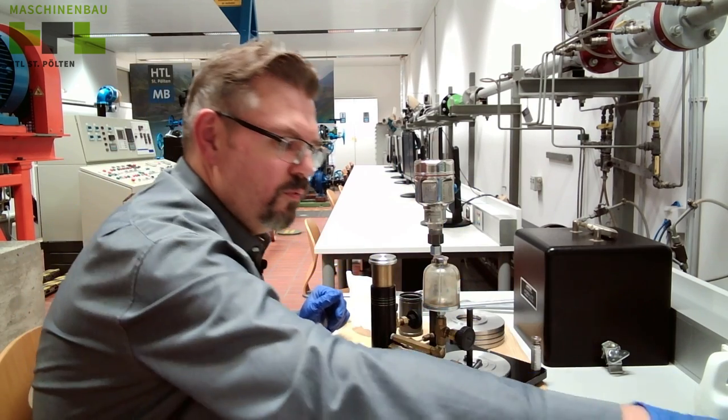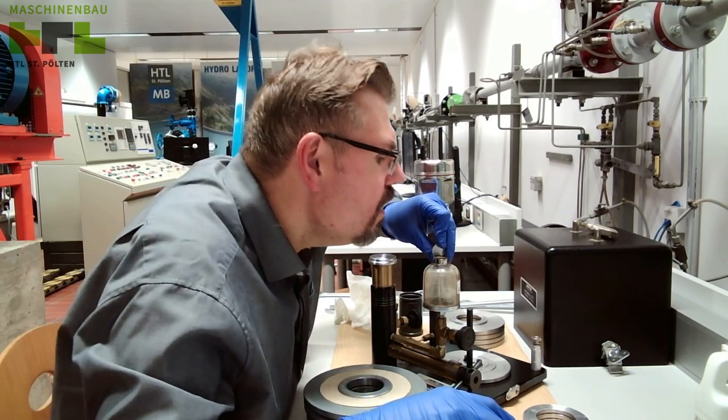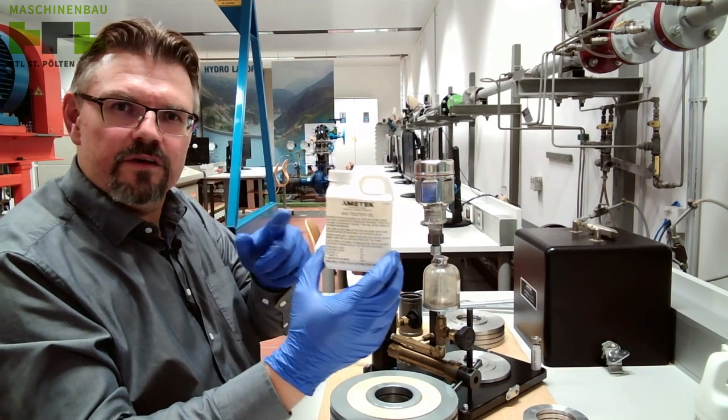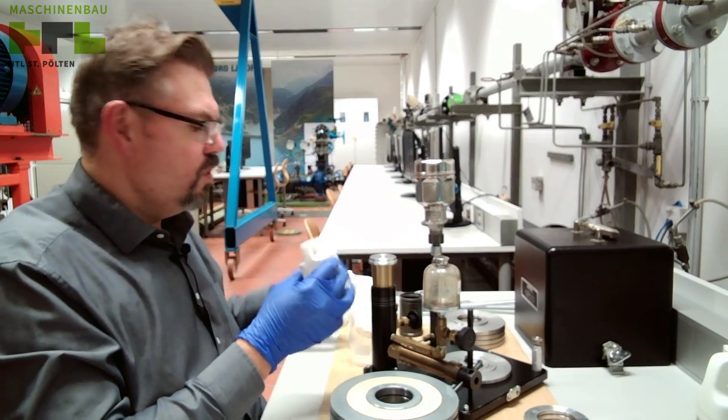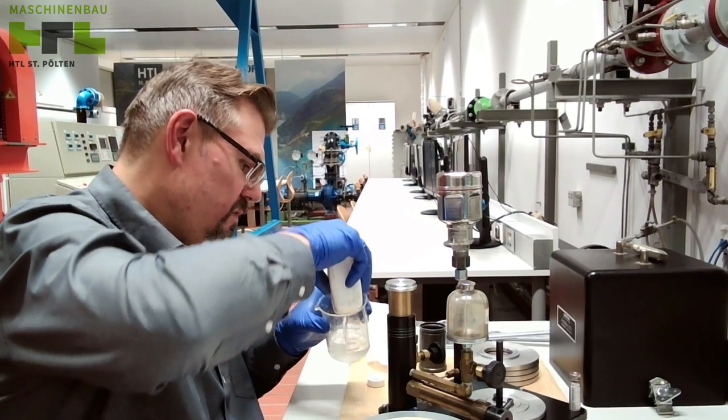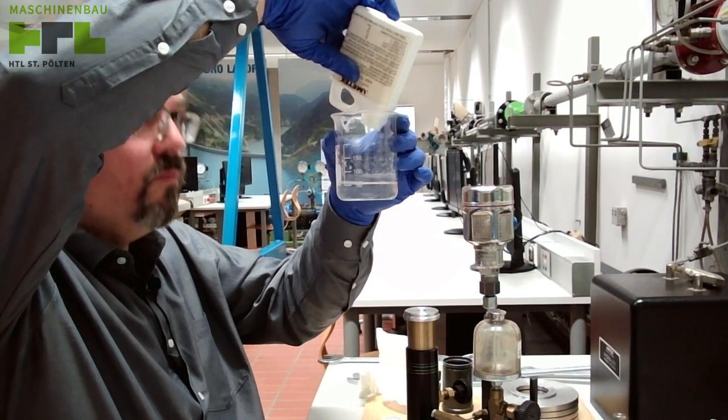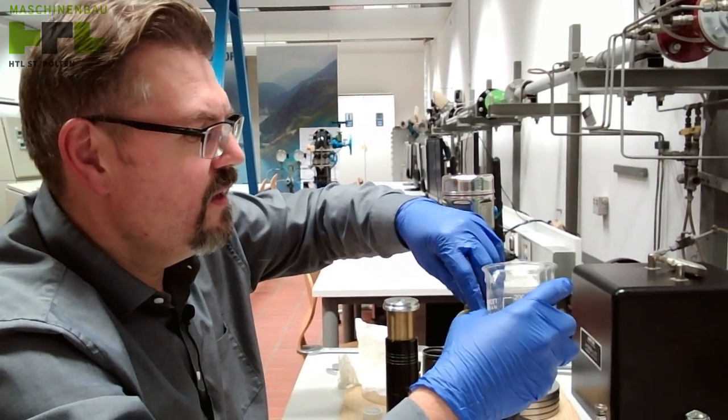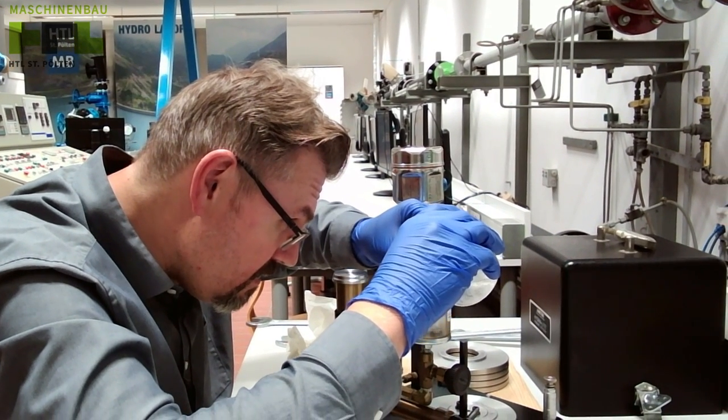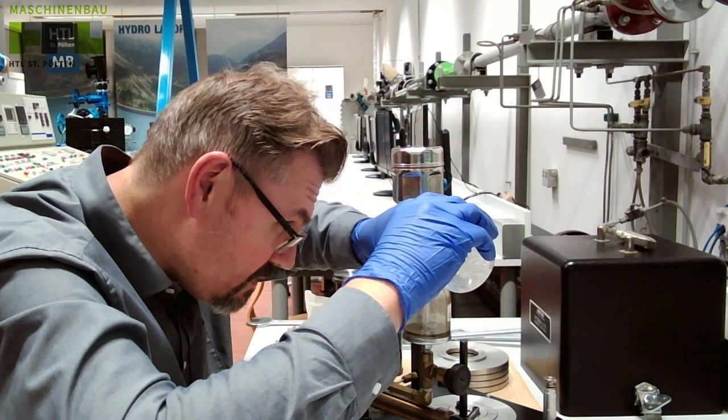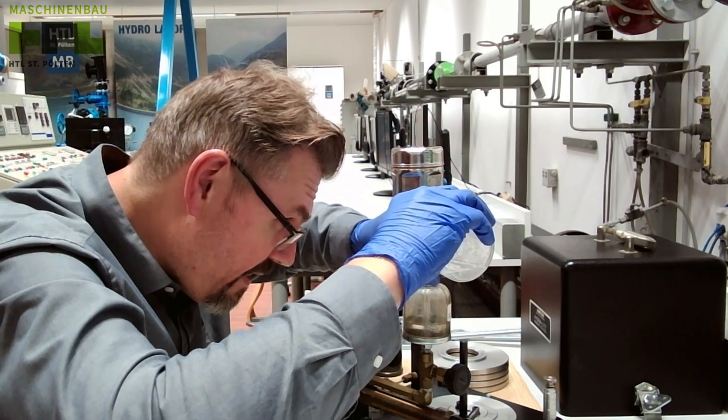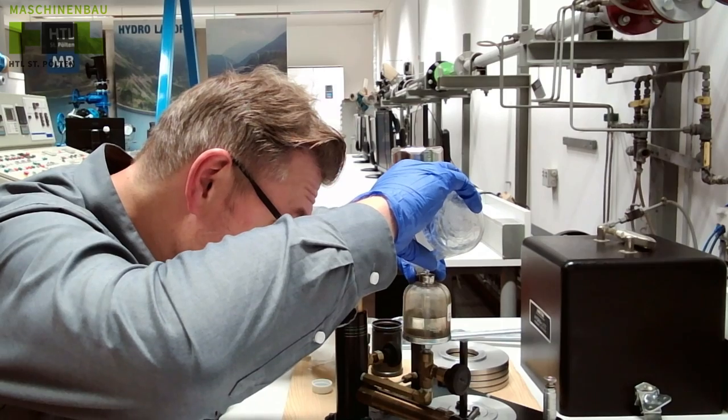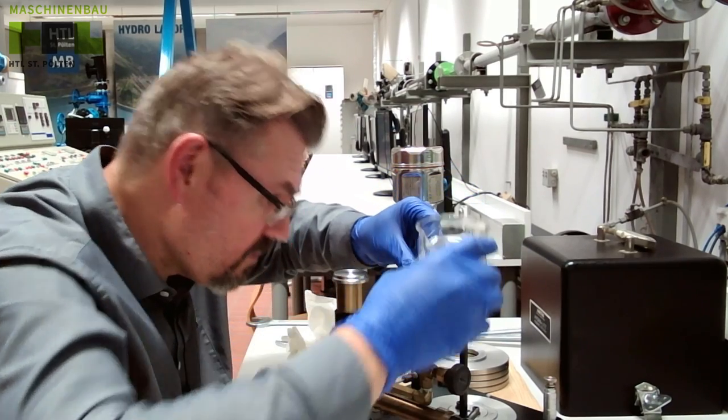I think we are ready to put in our oil. Like I said, this is silicon oil. I will use this. This is from the same manufacturer as this device. I am not exactly sure what it is. It must be very bright. It's silicon oil. From the price, I would say it's a mixture between diamonds and gold. It's just silicon oil. Of course it is expensive, because you need to have a really defined viscosity and so on to reach high accuracy.